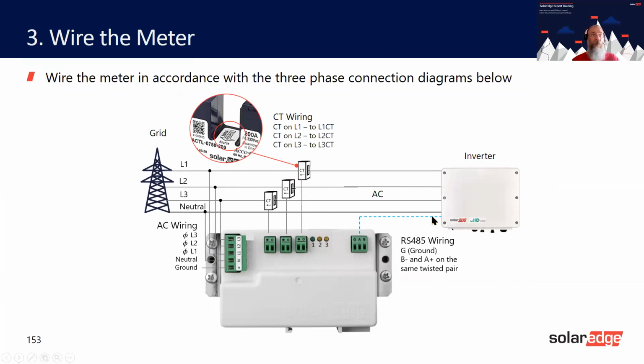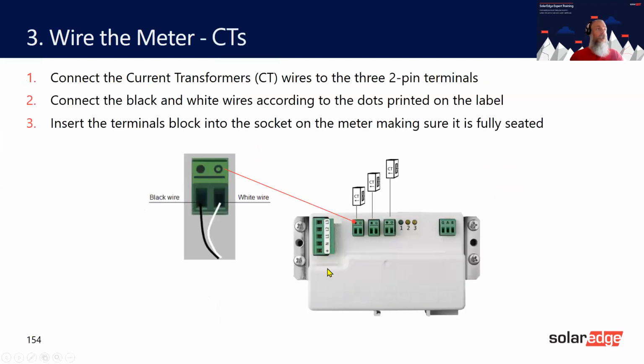And then we've got the RS485 cable, which is a twisted pair with B and A, B being the minus, A being the plus, and G being the ground. They don't need to be huge wire, just Cat5, Cat6 or RS485 cable can be used for these. With Cat5 and Cat6, you'll get a maximum of 100 meters distance. With RS485 cable, you will get a kilometer. It's self-explanatory, I think, here that you've got the white in this one and the black within this one. So hopefully we won't get confused.